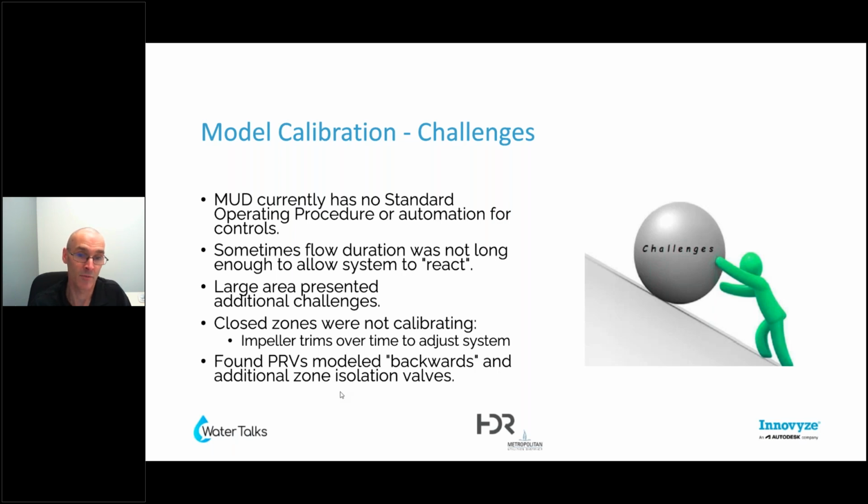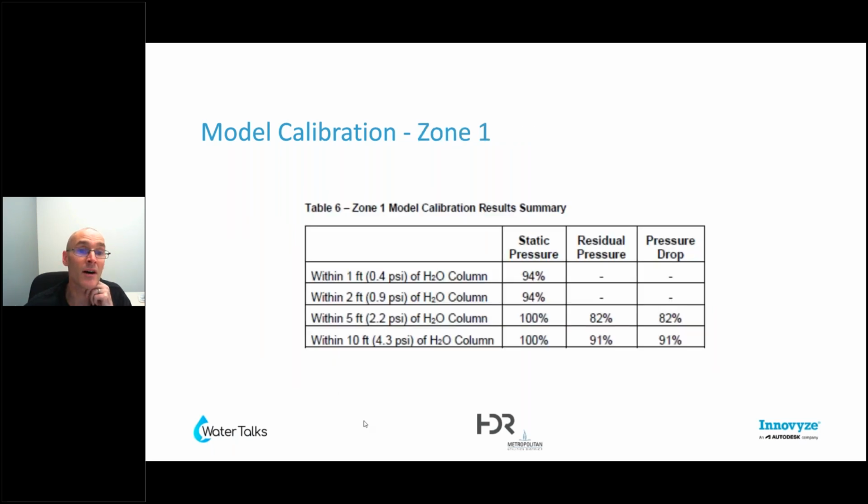So the calibration was really good for 2 things. One is it helped fix some facility issues for them, but it also got us a C-factor calibration. So finally, the results. This is interesting because, as you would expect, in zone 1, the gravity system where the pumps were reacting closer to what they were originally designed and manufactured for, we were able to get some really good calibration.